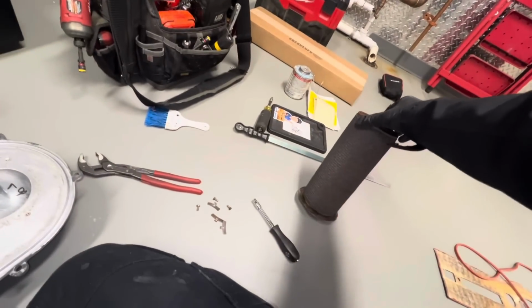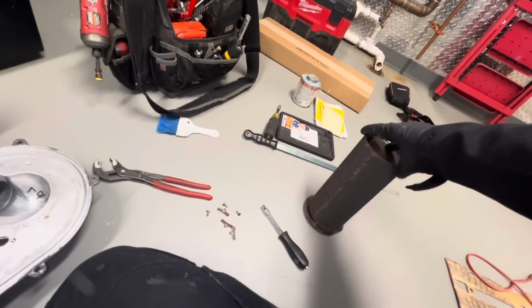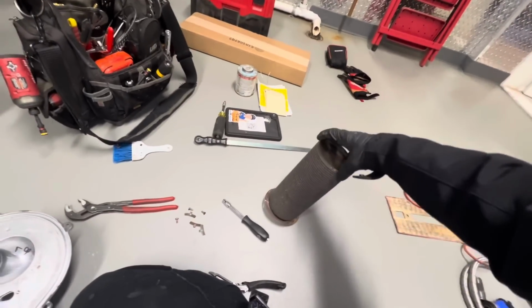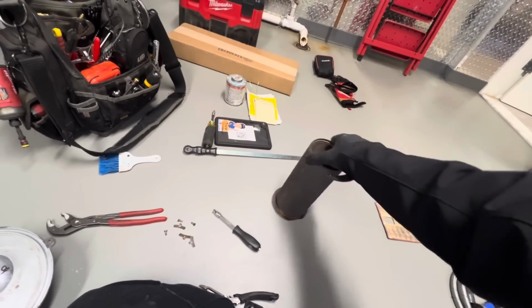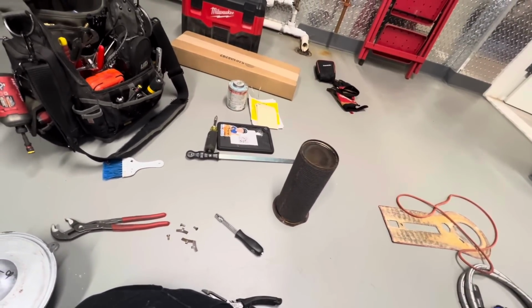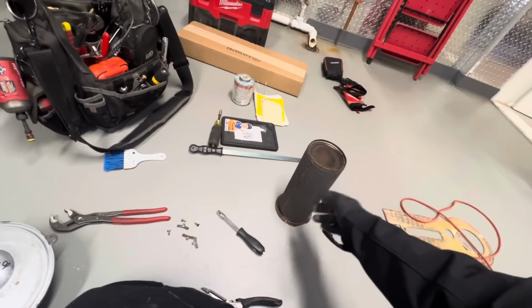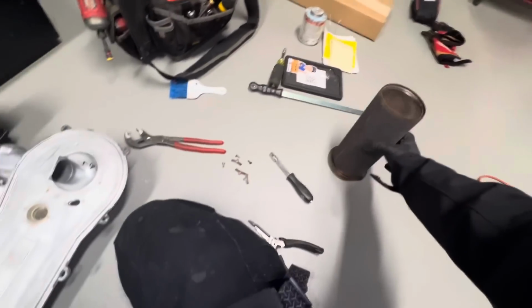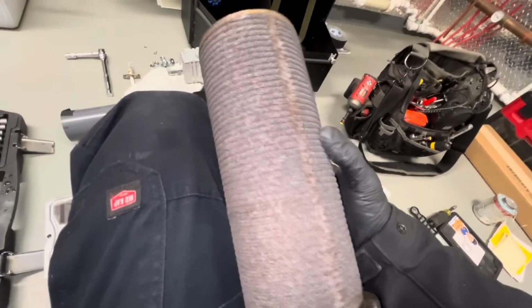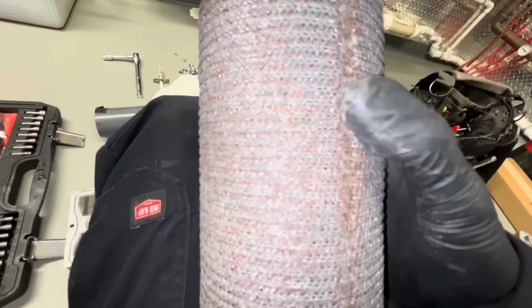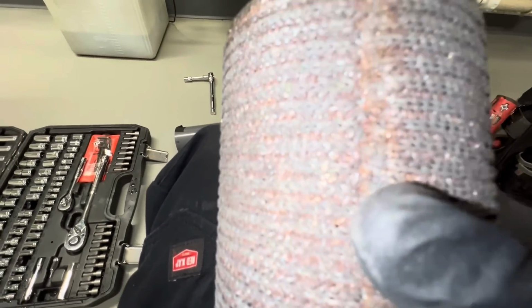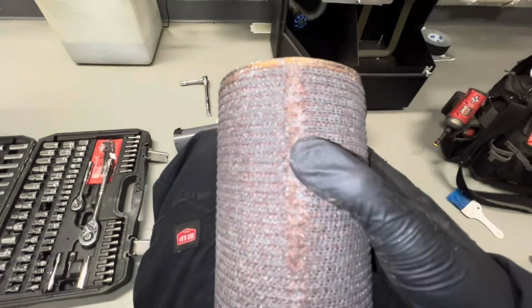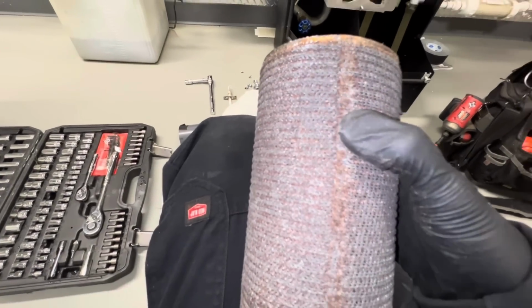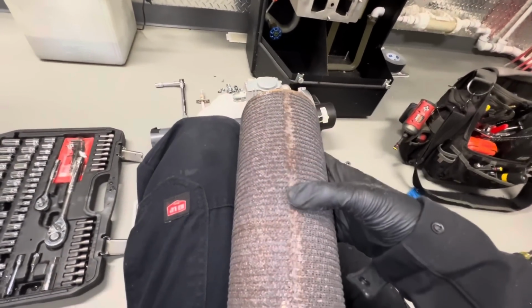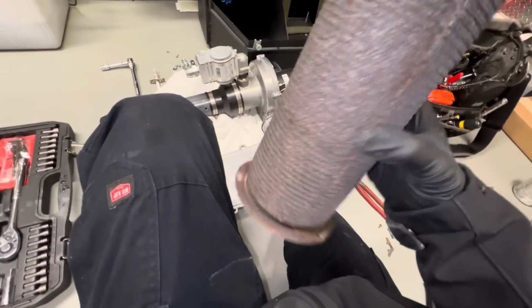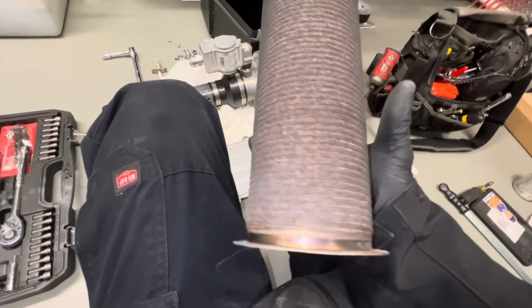And I may or may not use compressed air to blow this out, nitrogen, like I did in the Lochinvar video yesterday. Because that really got a lot of stuff out that you visibly couldn't really see. And probably get a good amount out of this, even though it's not too dirty. And you always want to inspect the mesh, make sure it's not broken anywhere. Like right here, there is a slight, looks like crack, but it's on the connection point, so that shouldn't be much of an issue.